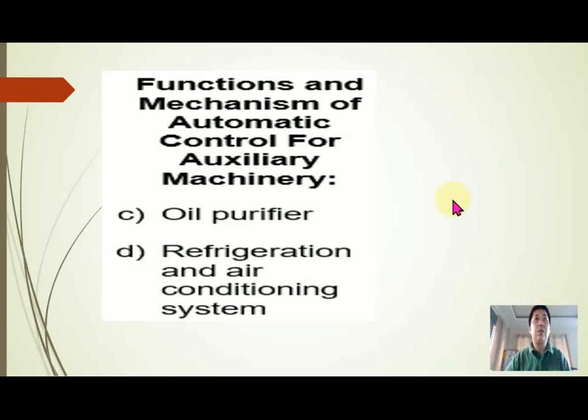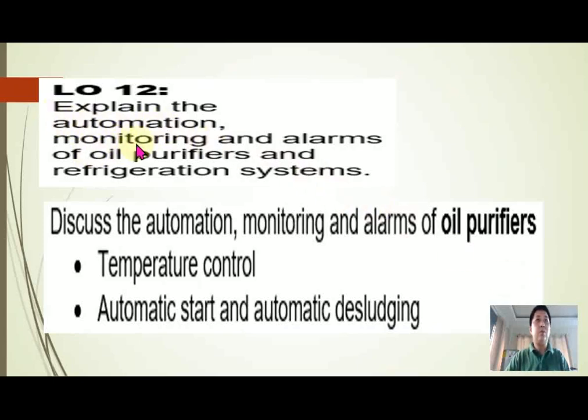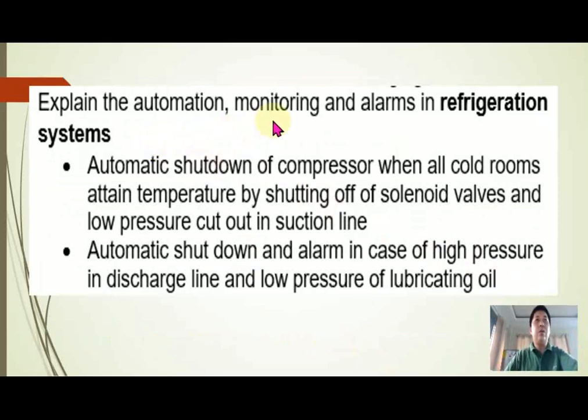Functions and mechanisms of automatic control for auxiliary machinery — oil purifier, refrigeration system, and air conditioning. Learning objectives: explain the automation monitoring and alarm of oil purifiers and refrigeration systems, automation monitoring and alarms, oil purifiers temperature control, automatic start and automatic desludging. Also explain automation monitoring and alarms in the refrigeration systems: automatic shutdown of the compressor when all cold rooms attain temperature by shutting off solenoid valves and low pressure cut-out in suction line, automatic shutdown and alarm in case of high pressure in discharge line and low pressure.